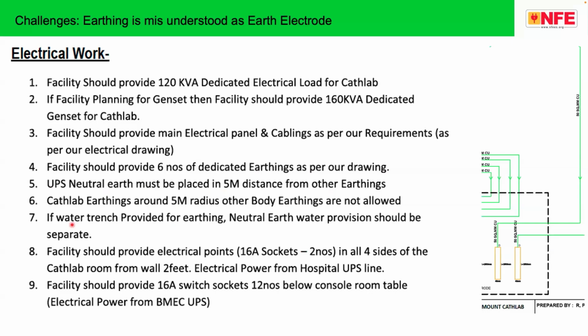There is a practice that some hospitals put water continuously into the earth pit in order to maintain less than 1 ohm, because if you don't maintain less than 1 ohm or 2 ohm, the equipment manufacturer will not give a guarantee. So now this equipment manufacturer made an interesting subject.